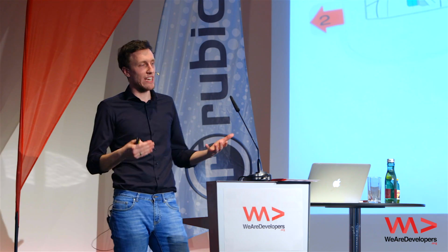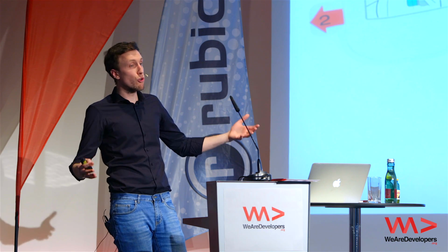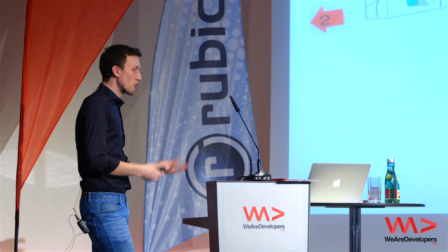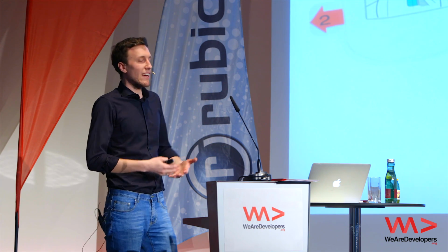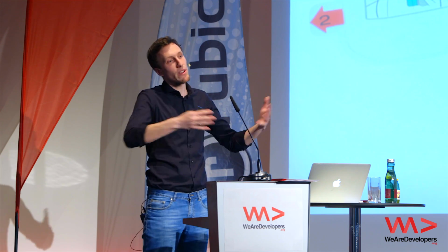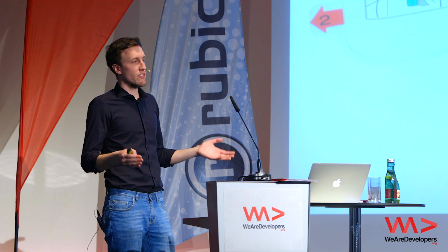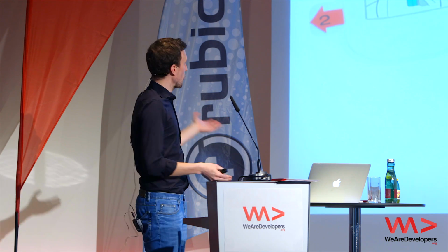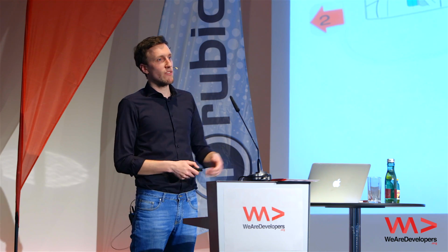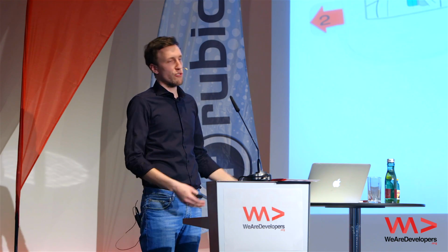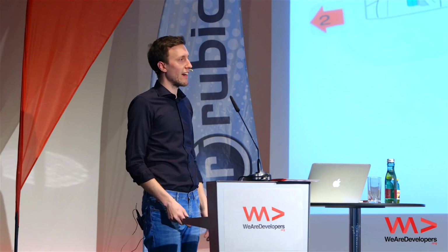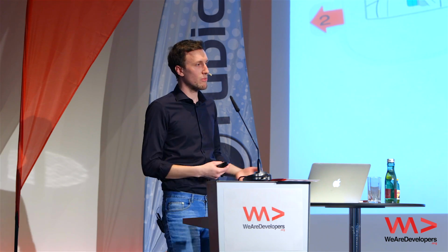Yes, of course, we are in Vienna, and there could be a tourist using the system. True, but in the end, it's more likely that somebody around will speak German, and therefore no possibilities, nothing to go wrong. Because the worst thing that could happen is you start the device, it switches through some kind of language selection, and then you end up with, I don't know, Spanish. Well, yeah, and how to go back from Spanish and whatever, and how to reconfigure it. Time is of the essence here, and therefore no selection.